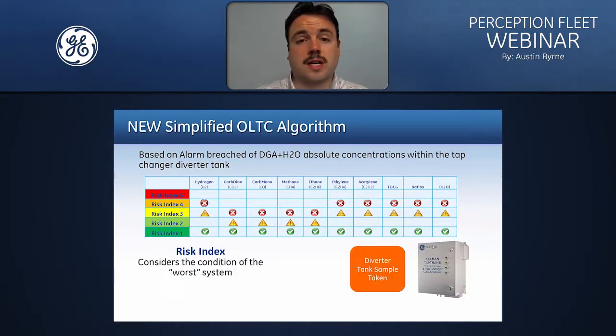So you can see the diverter tank sample is taken. If an alarm is triggered, so for an example in this particular screenshot you can see that hydrogen has triggered a high alarm, then a risk index of 4 is applied to that asset.